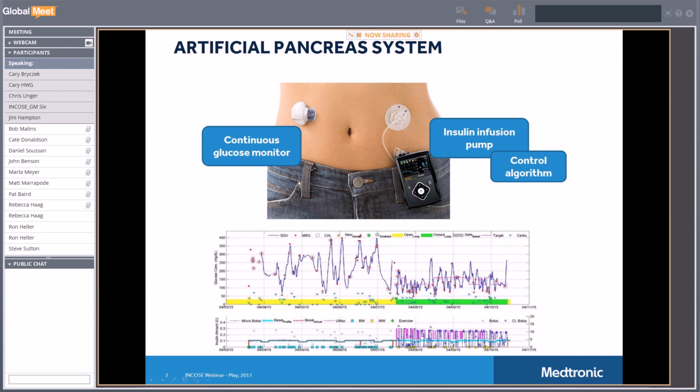So basically what we have is an insulin pump that's body worn, here shown on a belt-worn pump. It's about the size of a deck of cards, and it's filled with insulin and has the user interface. You can see a little screen on it and some buttons to control the therapy. And as I said, it contains the insulin itself, which it then feeds through an infusion set, a thin catheter that's implanted subcutaneously by the patient. And so they receive insulin delivery therapy that way.